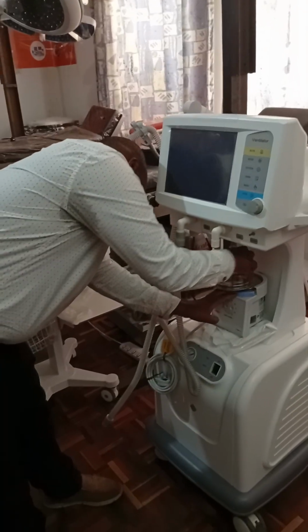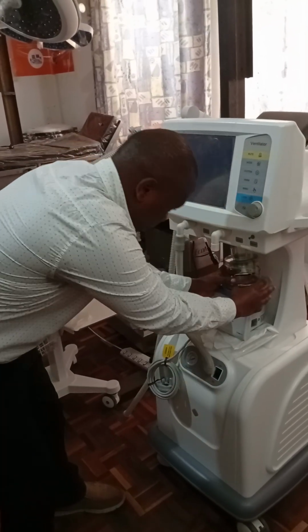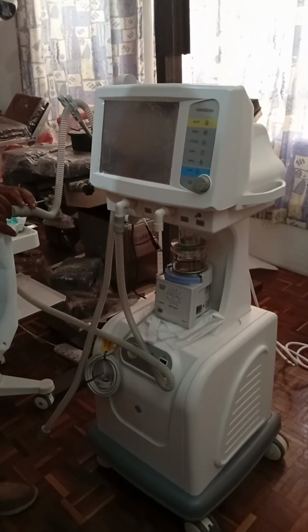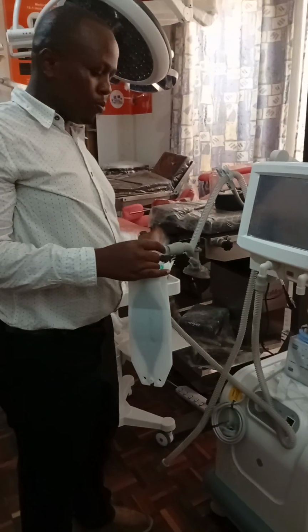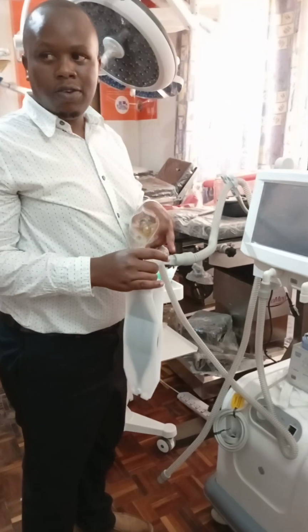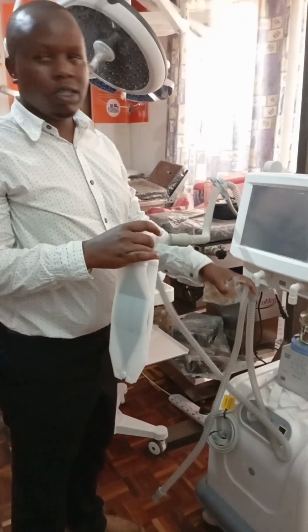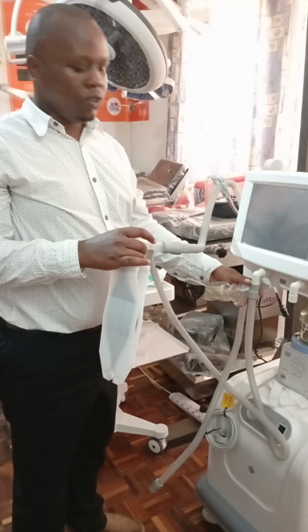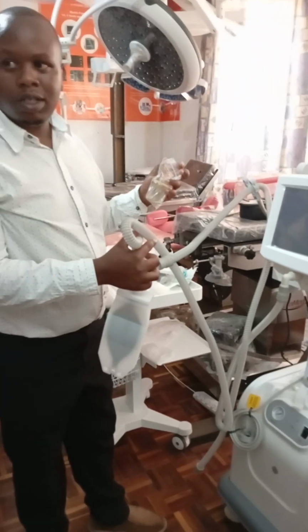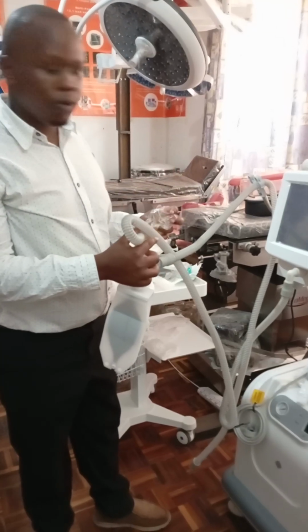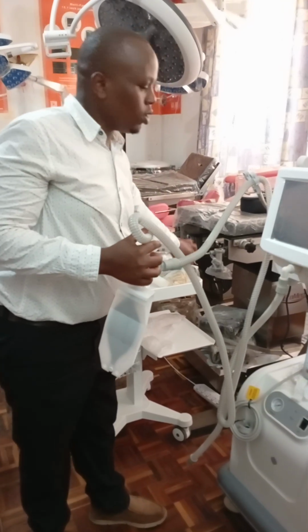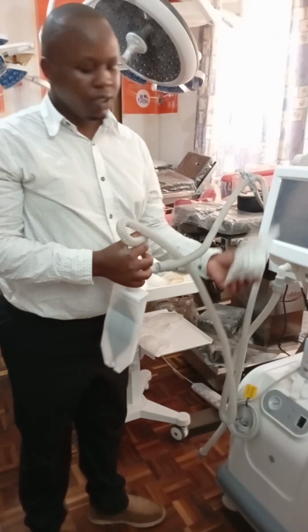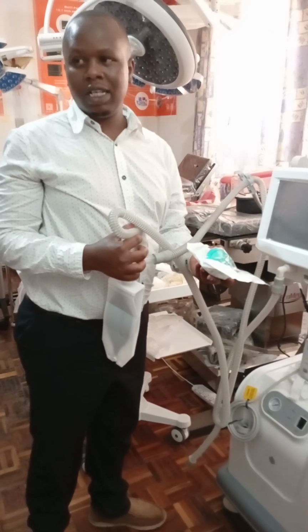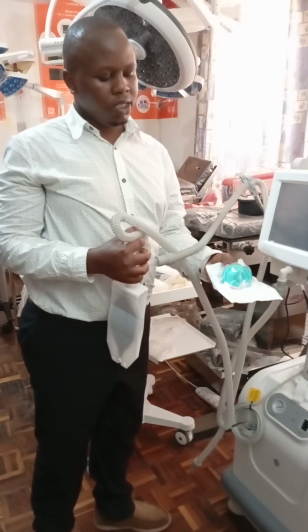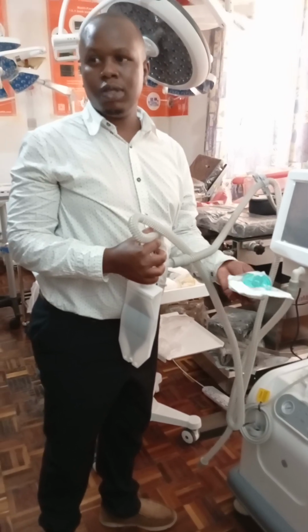Now from this water trap, it comes to the patient. From the patient, we have the one going to the expiration. In between the expiration tube, we also have a water trap. Another one. Yes, so you'll have two water traps for going to one connection. At the expiration end here, you'll need to connect this bacterial filter. This one needs to be exchanged every 3 months.